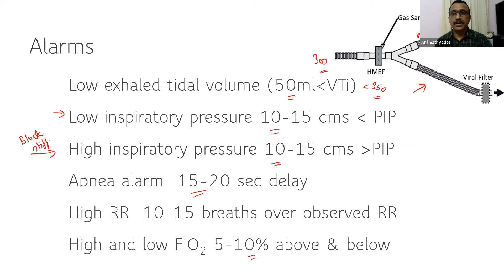Apnea alarm, especially in a patient who is spontaneously breathing in a weaning mode, the typical default is 15 to 20 seconds. And if the patient is not breathing, it would go into a backup mode also. Higher rate alarm is 10, and FiO2 is again 10% above and below what we have set. This is how you set the alarms, and all the alarms should be switched on. That is how the ventilator will try to tell you that there are problems. Please go and troubleshoot any alarm that sounds.